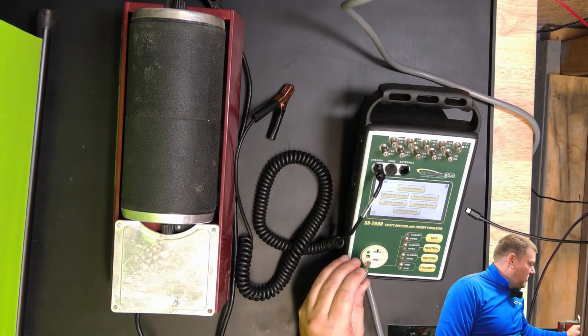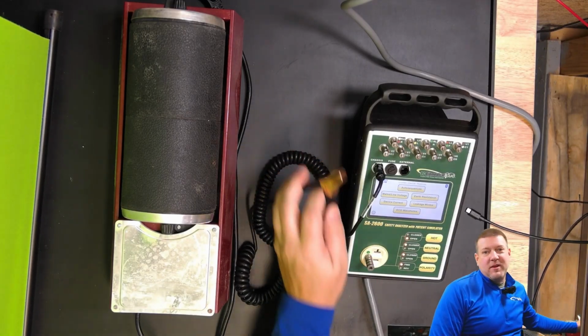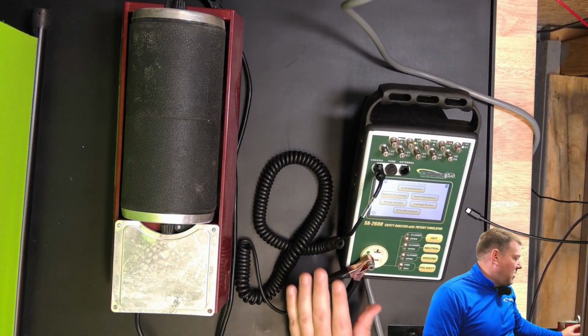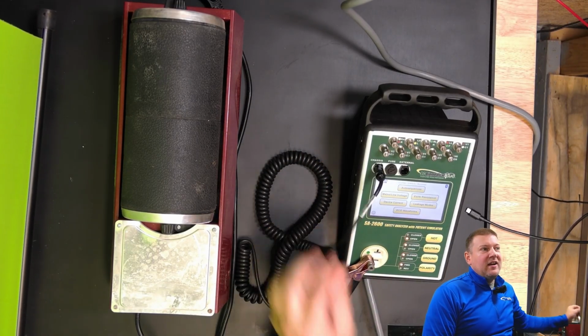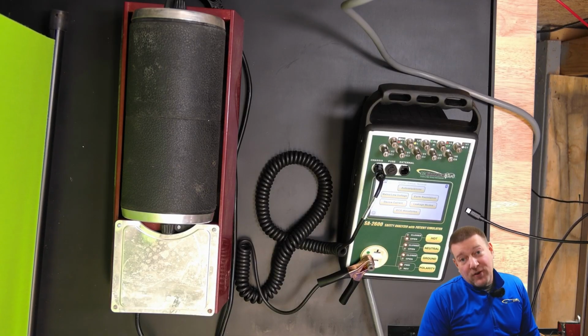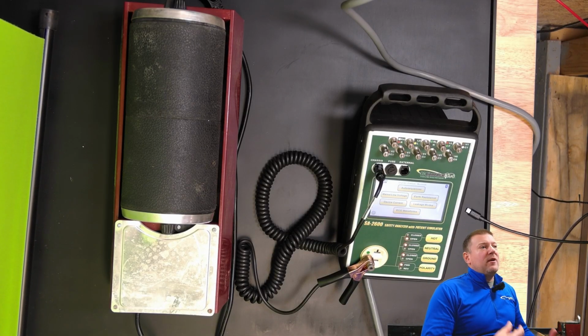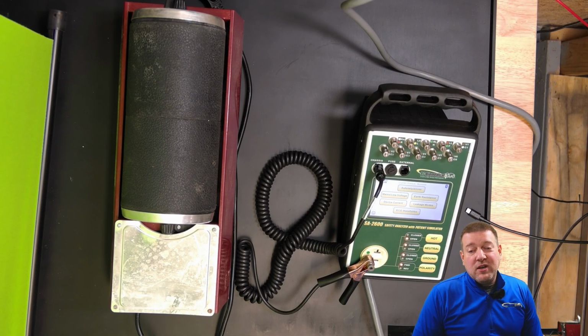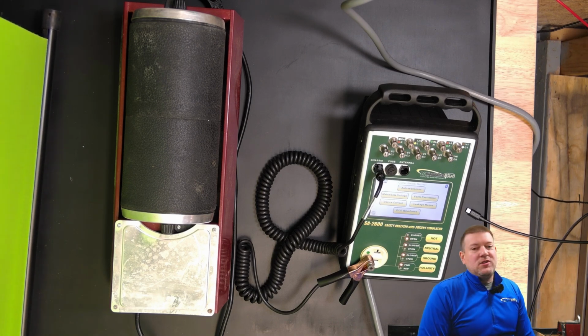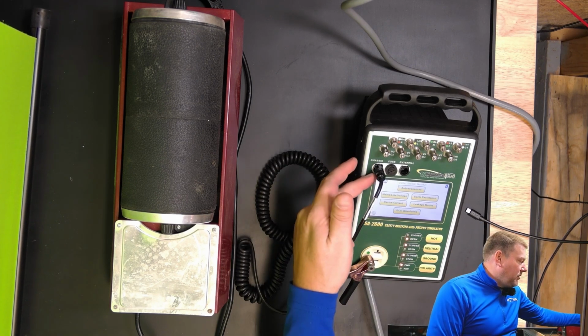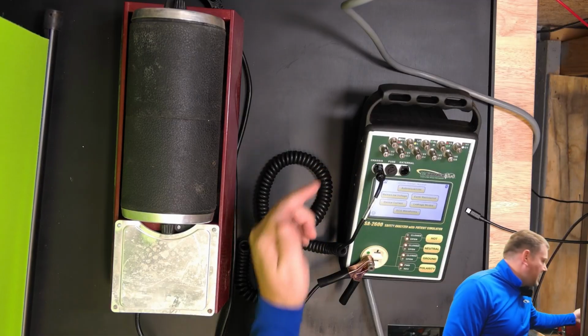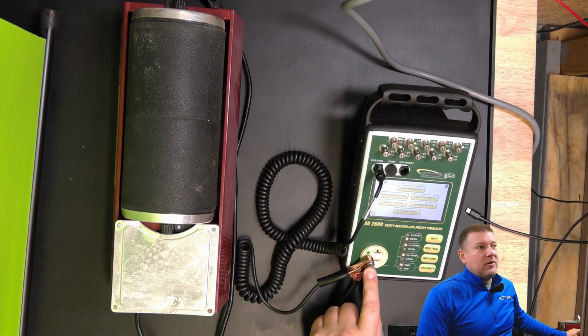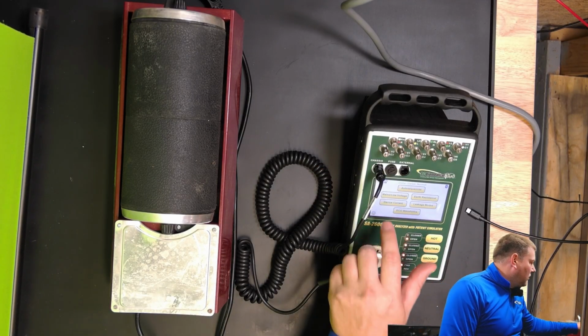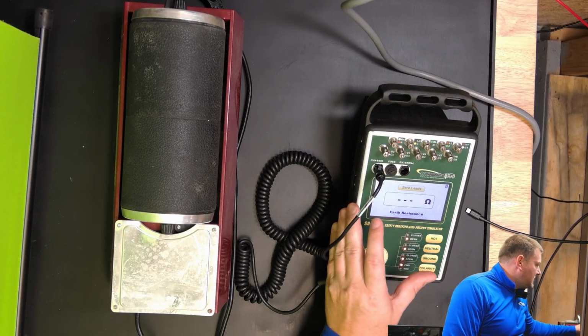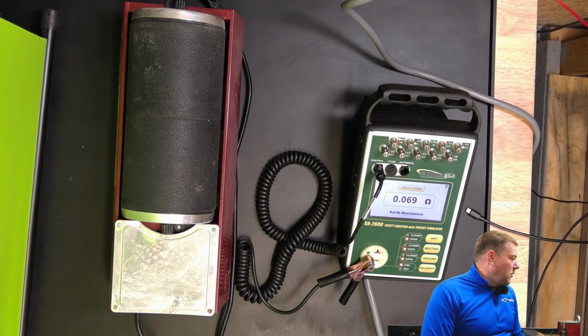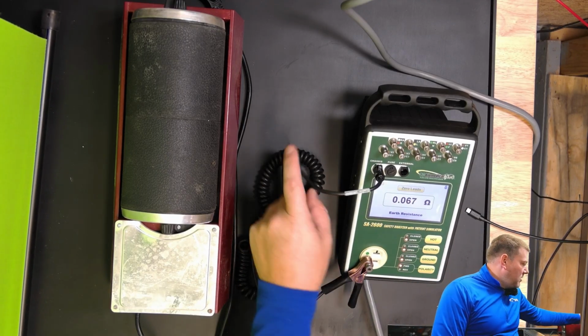First thing that we're going to do when we get a new electrical safety meter is check out and make sure that the test lead is functioning correctly. Anytime you unpack your electrical safety meter, when you get to a new job site, first thing you should do is this very check. You're going to plug it in, like I've got mine up here on the chassis. We've got our little grounding electrode right here, and we're going to go into earth resistance, and we're going to see how low it is. All right. Move it around a little bit, make sure it's good.